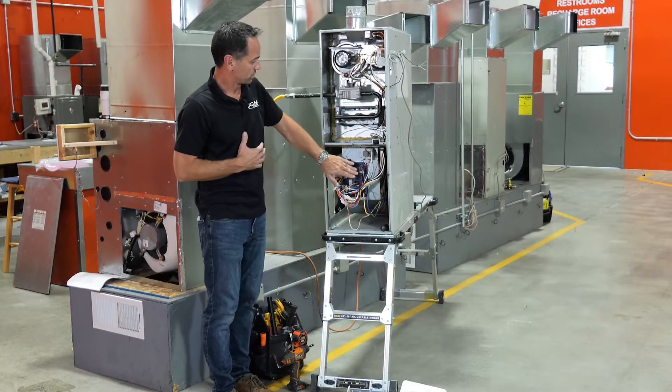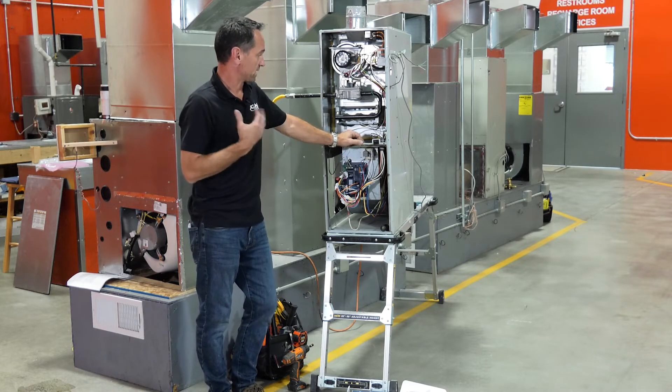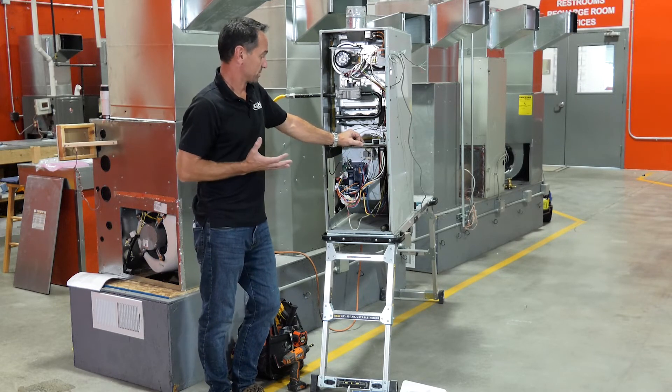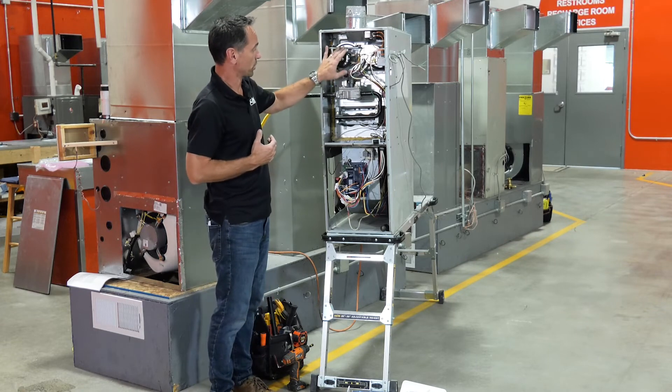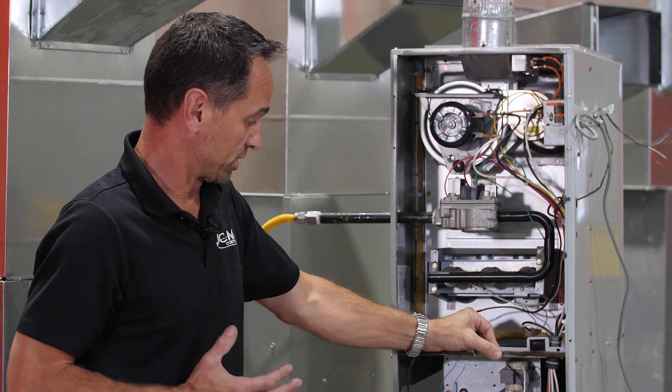Now that we have our ICM 2812 kit installed in this Carrier/Payne furnace, we've tested all the sequence of operation, inducer motor, hot surface igniter, gas valve, blower. Everything is working the way it should.